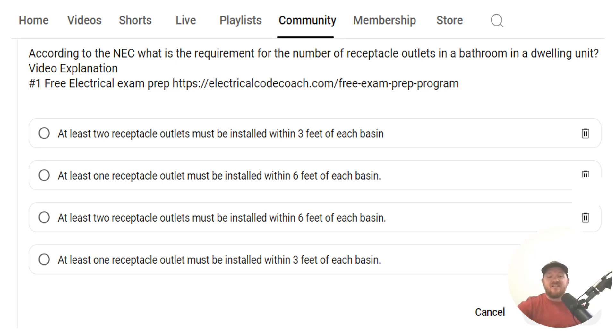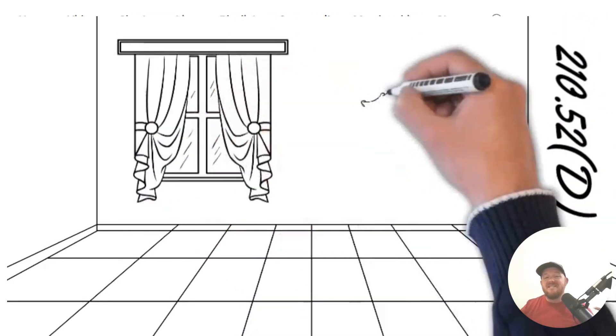And the correct answer is D. At least one receptacle outlet must be installed within three feet of each basin. And for this one, we're going to head to 210.52D.